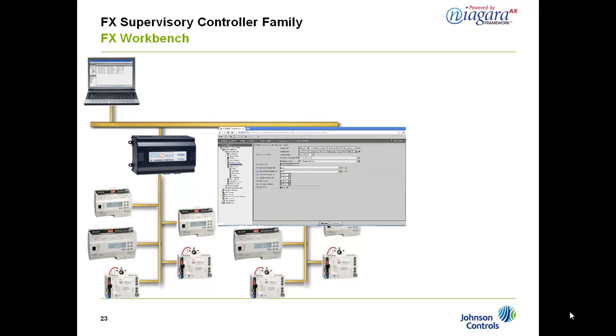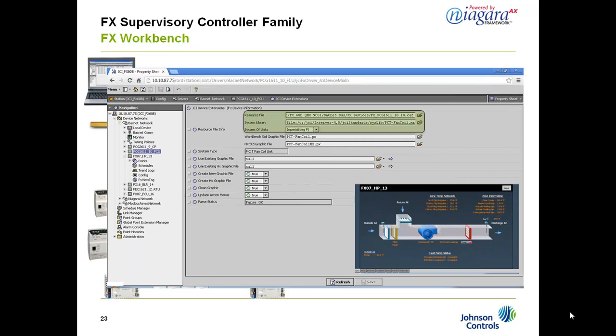All these features of the FX Supervisory controllers are engineered and configured via the FX Workbench tool. FX Workbench is included as part of the FX Supervisory controller's embedded web user interface, and it is also offered as a client application running on a PC. Johnson Controls has added some field productivity enhancements to the FX version of Workbench. FX Workbench has a wizard that assists the integration of Johnson Controls field devices by automatically mapping their points into the station database and by automatically creating graphic views for the system user interface.